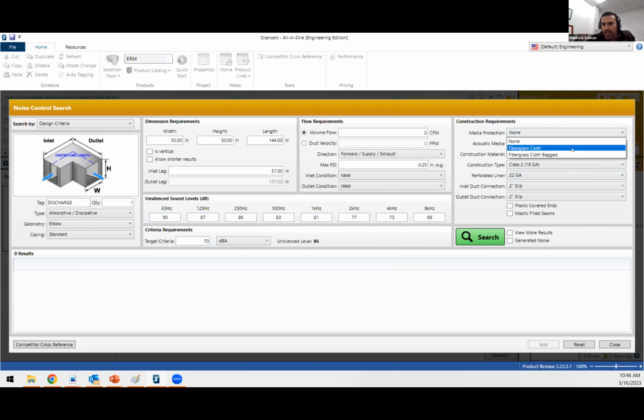And when you look at that, you can see that you could add flanges if you want to attach to the fan, of course, because it is bigger than 48 inches. Sheet metal that you can get from most manufacturers is 48 by 48. Now you're going to get those dimensions in multiple components. That's when it doesn't let you do flanges that are attached. Then if you want that to be low leakage, because it's going to be situated outside, you fill every single potential gap, because we're using a snap lock to build the silencer, with mastic fill seams. If you want to protect them so that they don't get banged up in shipping, you could add plastic cover ends. And then you're going to tell the software, hey, find me a silencer that meets that.